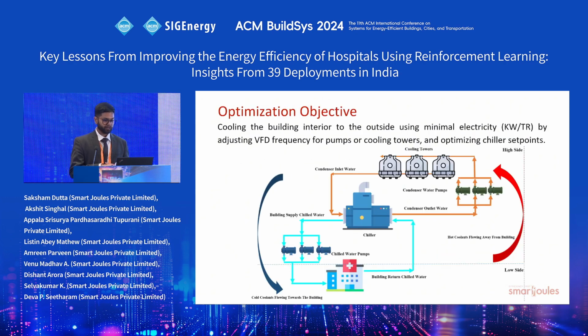With this in mind, we developed automation software that could produce cooling of the building interior relative to the outside using minimal electricity, by adjusting the VFD frequencies and cooling towers and optimizing the chiller set point.